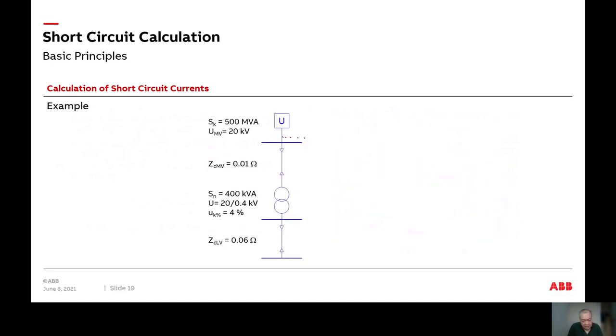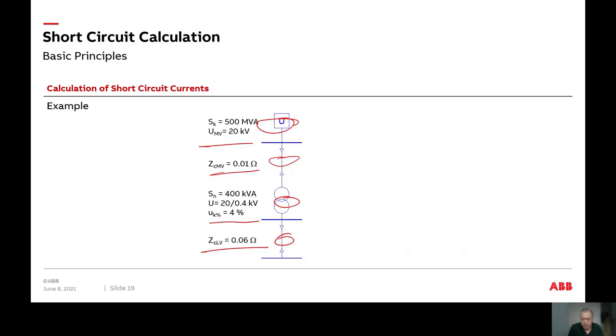With a single line showing utility, medium voltage cable, transformer, LV cable, and all parameters, we can find the short circuit current. As a designer, I don't want to spend too much time calculating. Most of the time I work on a rough estimate of the short circuit current after the transformer, then use software — like EasyPower or ABB's DOC Web — to calculate and understand the system so I can size components correctly.